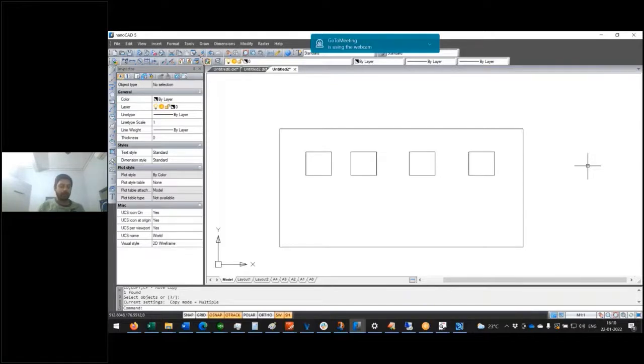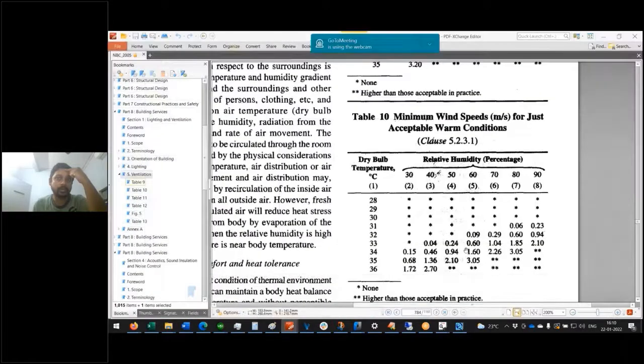Sir, I had a doubt. Sir, this CMH calculation, can you please repeat, sir? Actually, the CMH calculation, this cubic meter per hour. So the ACH we can get from the manual. The standard ACH is defined, whether it is a warehouse or whatever, we can select from the table. And as you mentioned, the cubic meter per hour, does the room volume have to be taken, or the opening volume? No. This is the volume of air that will flow through that opening.